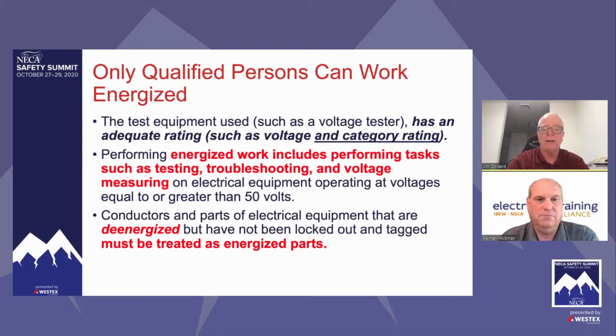And when they opened it up, they saw some terminals in there, and they looked at each other and said, no way, that's 4160 because they're too close together, but it might be 480. So let's test it. And when you put a 600 volt tester across 4160, it goes boom. And fortunately, we didn't have a serious injury. But what does that tell you? As soon as somebody cannot determine the nominal voltage, they are not qualified.